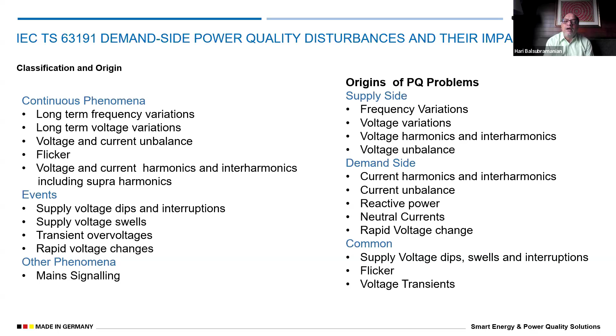So whenever there is a power shutdown in our plants, we should also start measuring the voltage. How good is the voltage quality? If my loads are all shut off, how good is the supply I am receiving? That will also be a good exercise whenever there is a shutdown of your loads for maintenance purposes. Thereby you can also check the origin of power quality problems from the supply side as well.